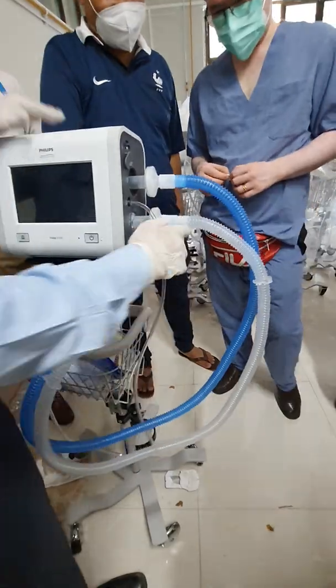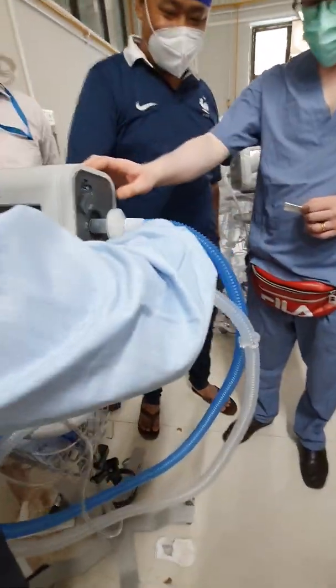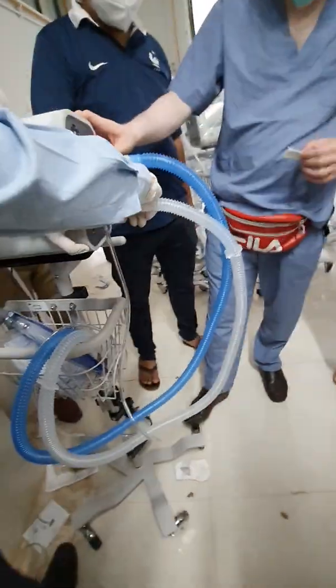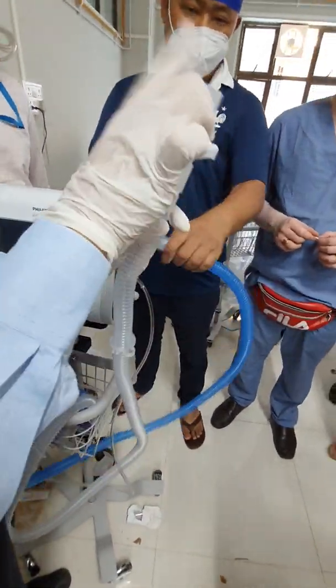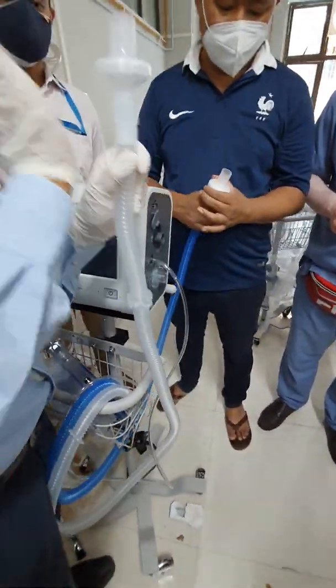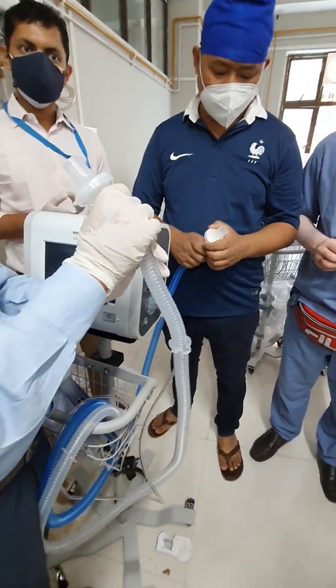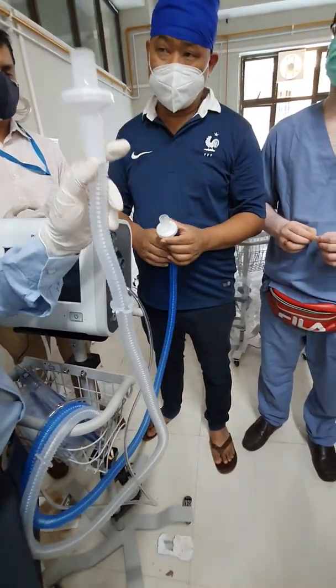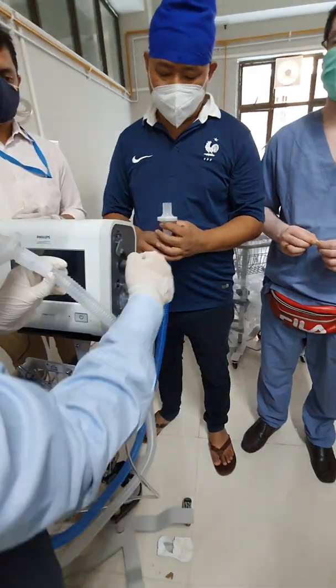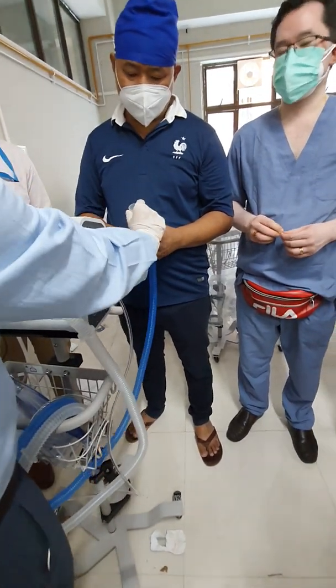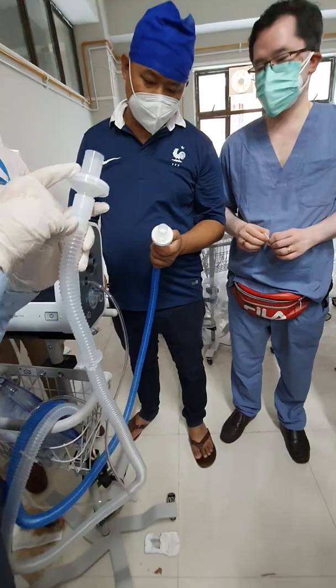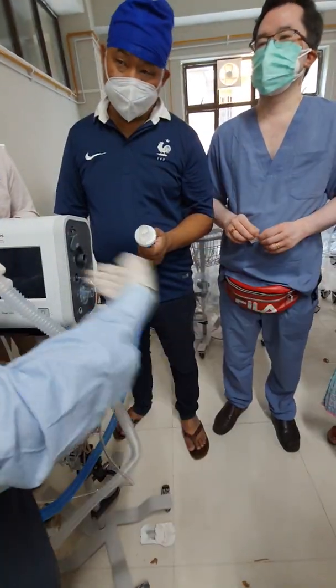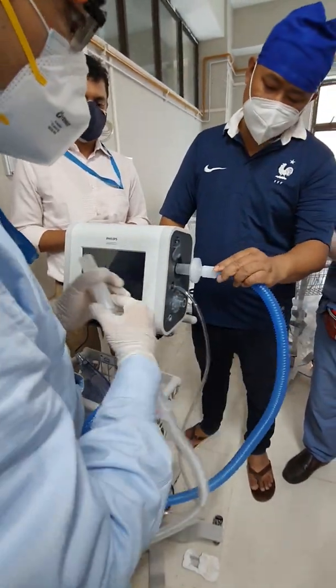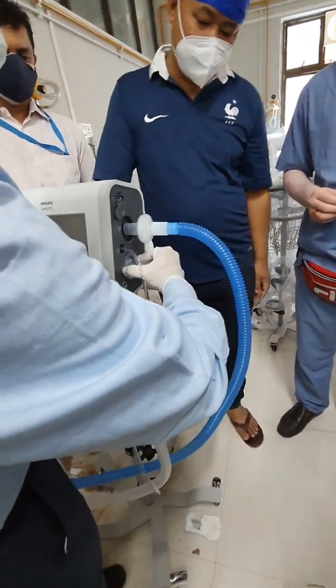Now look into the expiration side specifically. At the expiration side we have a filter. This filter is a bacteria filter, mind it. Please don't put an HME here by mistake. It should be a bacteria filter. This filter is optional on the inspiration side, but here it is mandatory. Why? Because it is the expiration side. After this bacteria filter, you have an exhalation valve.